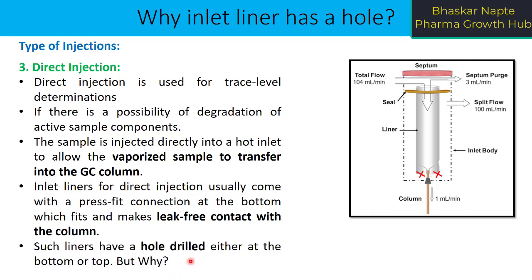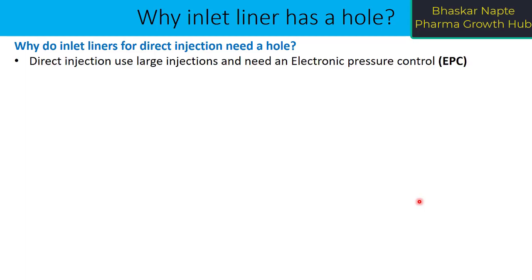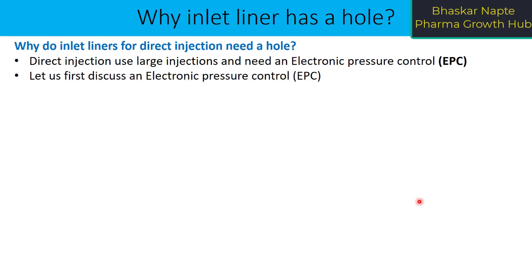Now, such liners have a hole drilled either at the bottom or top. Why? This is the point we are going to talk about today. In this particular diagram I have not shown this hole on the liner, but I want to explain why there is a need for a hole on a liner in direct injection mode. Direct injection uses large injections and needs electronic pressure control. We understand that direct injection is used for trace level component analysis where concentration is low, so you have to go with higher injection volumes like 4 or 5 microlitres, and in such a situation EPC is used.